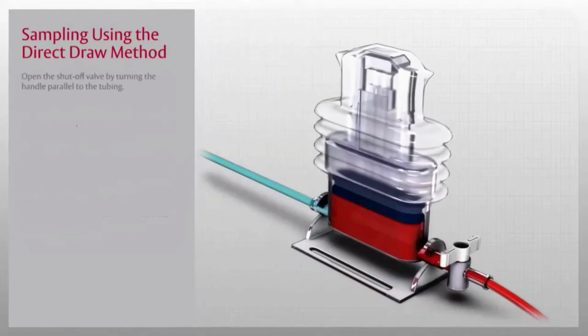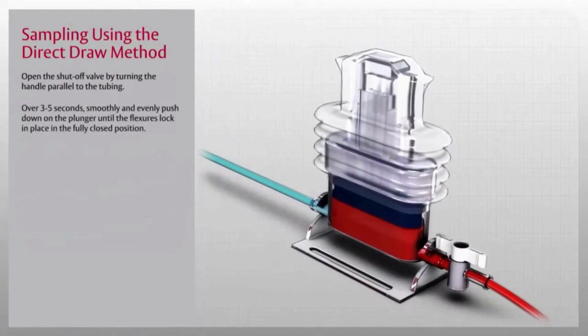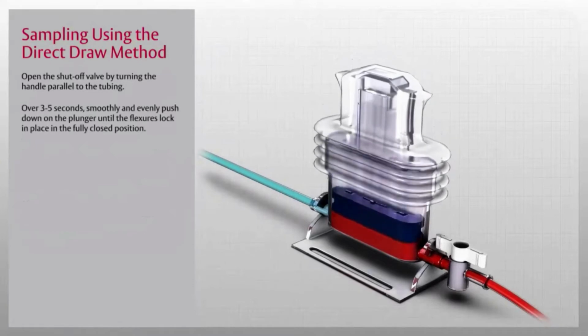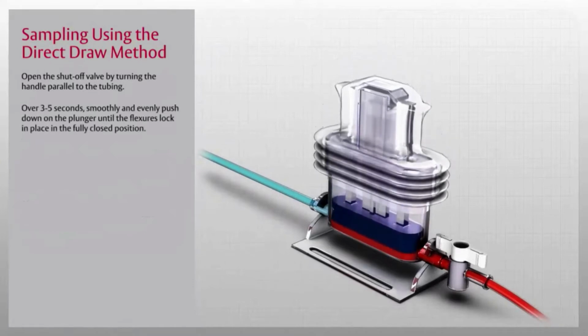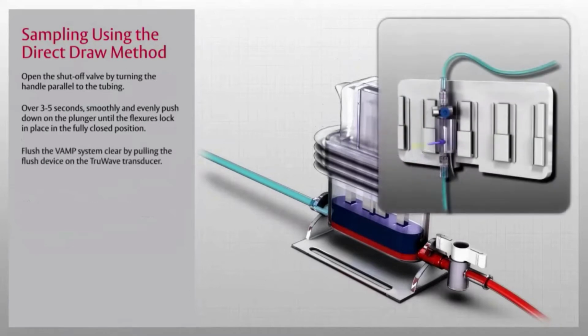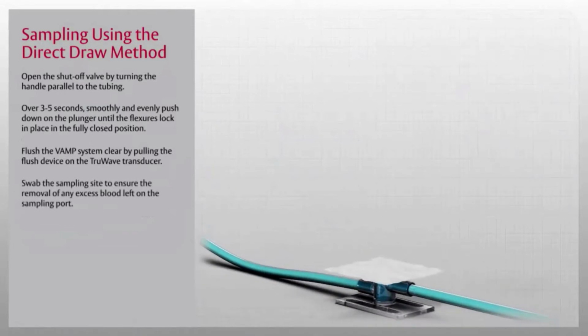Once you have the samples drawn, you need to reinfuse the blood and clear the line. To do this, open the shutoff valve by turning the handle parallel to the tubing. Next, over 3 to 5 seconds, smoothly and evenly push down on the plunger until the flexures lock in place in the fully closed position and all of the fluid has been reinfused into the line. Finally, flush the VAMP system clear by pulling the flush device on the TruWave transducer and swab the sampling site to ensure the removal of any excess blood left on the sampling port.